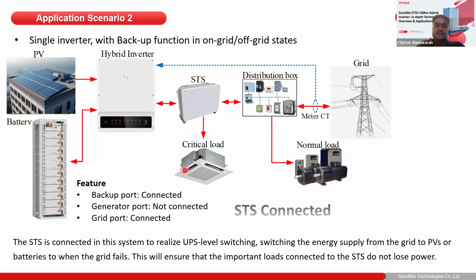Now, this critical load is basically connected to the backup port of the STS. So this is your backup load. In this case, you have no diesel generator connected. It's just the critical load, the STS, your batteries and your PV. And then in the occurrence of grid outages, your battery and then your PV, if there's PV available, supply power to the critical load through the STS.